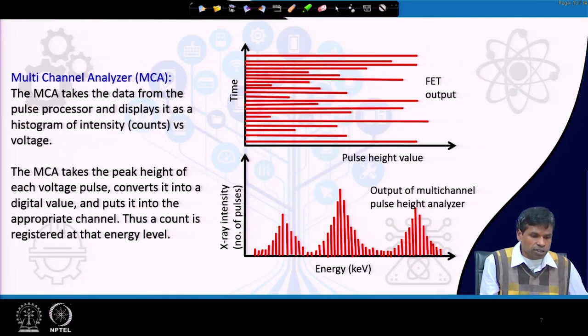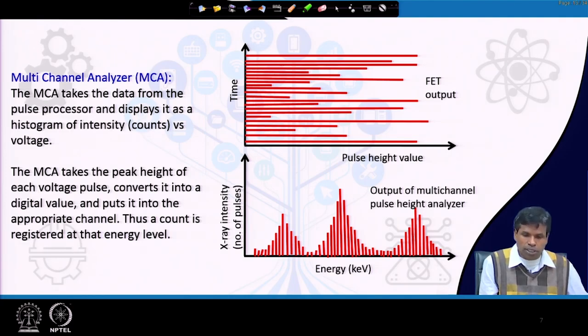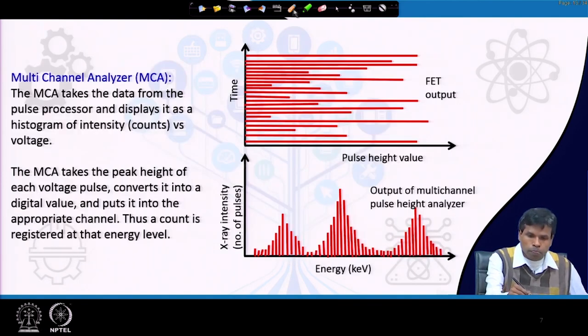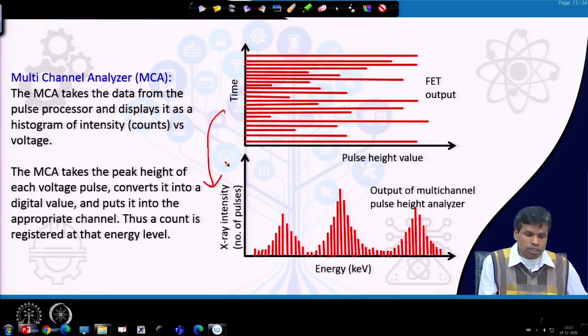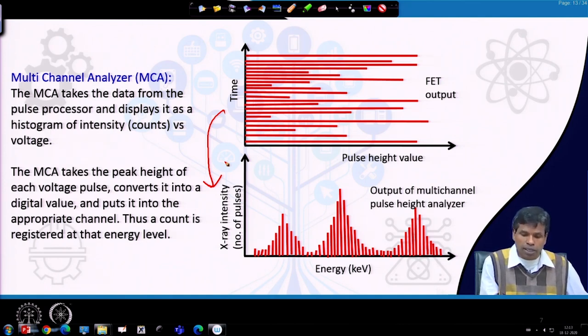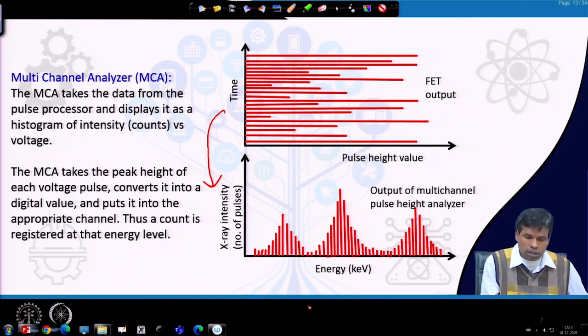We then have a multichannel analyzer, which takes data from the pulse processor and displays it as a histogram of intensity counts versus voltage. From there we get a spectra. The multichannel analyzer takes the peak height at each voltage pulse — there are several channels, and depending on the energy, different channels are activated, producing the spectra with a particular energy for each channel. The count is registered against each energy level.